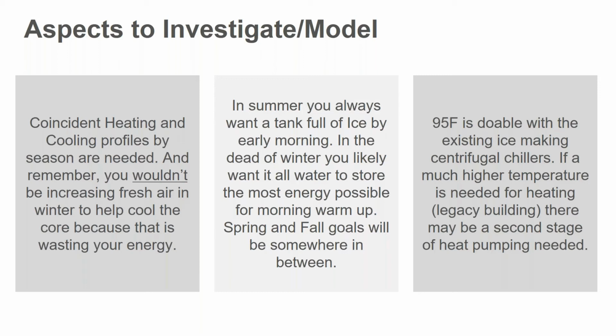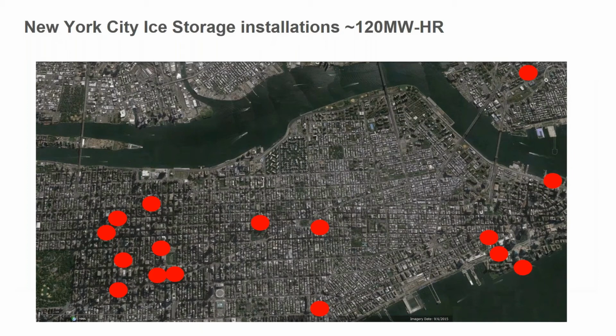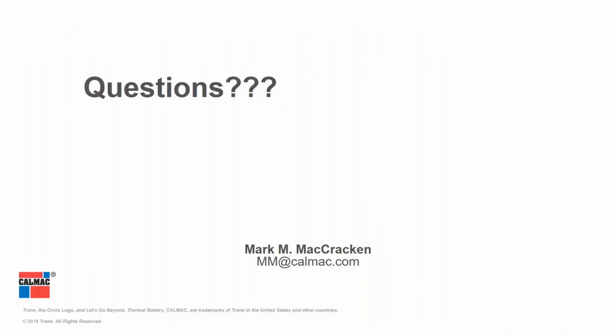But there seems to be plenty of push in the amount of storage that you'll have in the winter if you size by the summer cooling load. And then 95 is doable with existing ice-making centrifugal chillers right now. If higher temperatures are needed, you'd have to look at either a second stage heat recovery chiller or a screw recovery chiller that can do a higher lift. But certainly very doable. So there's lots of energy storage in New York City now, in a lot of the legacy and some of the new buildings. And so there's a lot of thermal energy and heat in these buildings that could be used with a storage source heat pump system. And so with that, I am happy to take any questions you may have. Thank you very much.